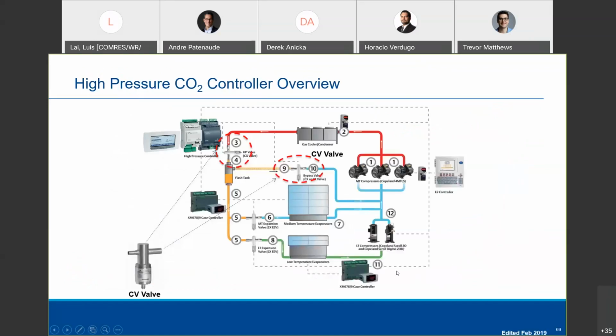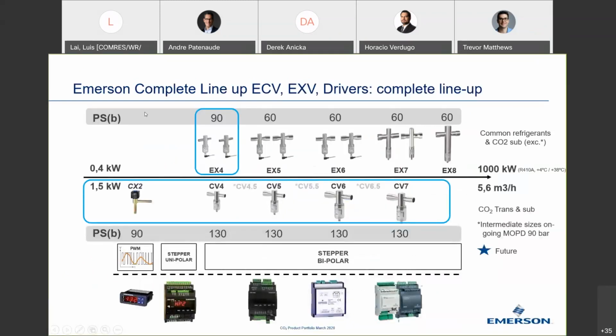High pressure valves, we've got about 10 minutes, so I'll move along here. The CV valves are there to control high pressure into the flash tank, and as I mentioned earlier, bypass to medium temp suction. And there's a high pressure controller that can drive those. This is the Emerson Pro CO2 high pressure control. There's a family of valves. Emerson has the EX family that's been around for 15 to 20 years.